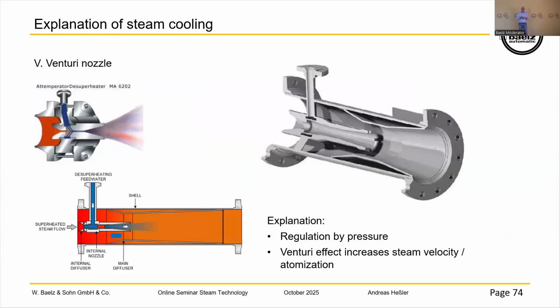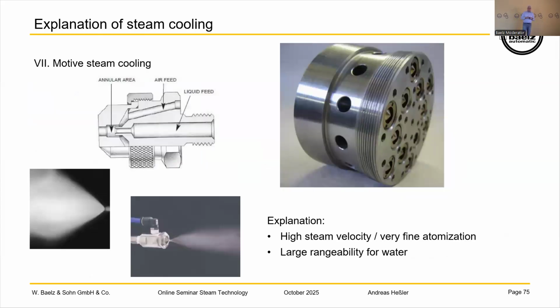The Venturi nozzle works with the Venturi principle. It is also over pressure, of course, but in this case we are using the higher increase of the velocity of the steam to atomize the water droplets. And the last one is the motive steam cooler. I already told you it is a very fine atomization because we are using the high pressure steam to vaporize the water.